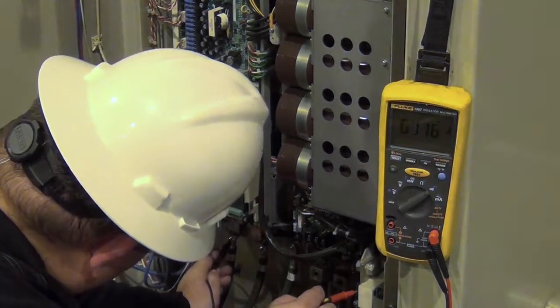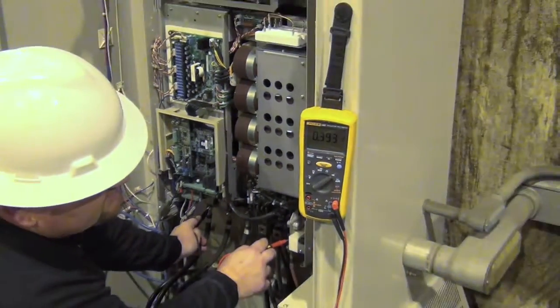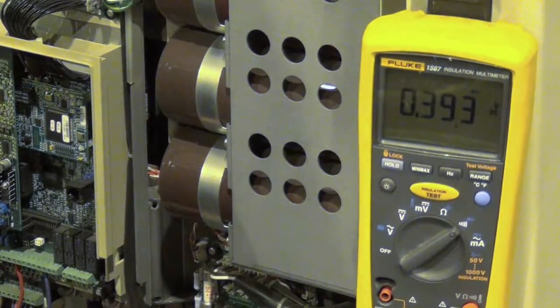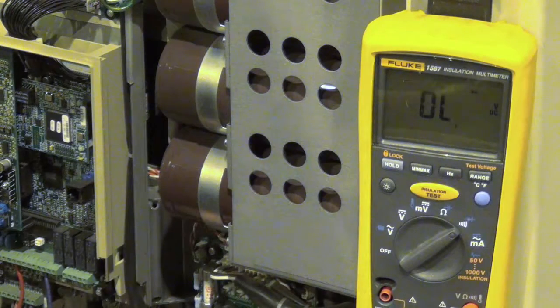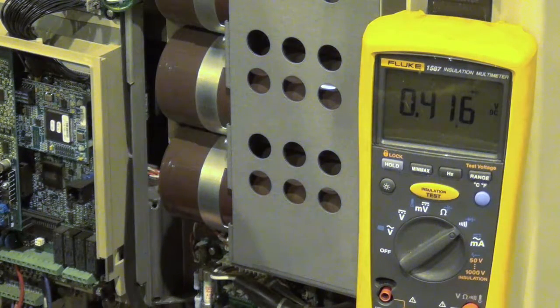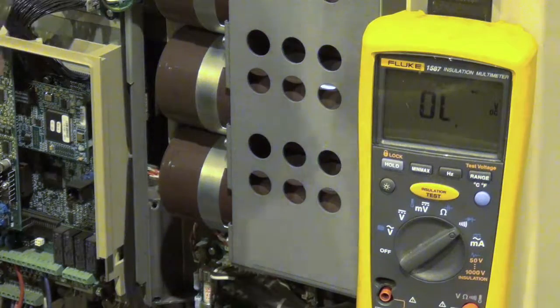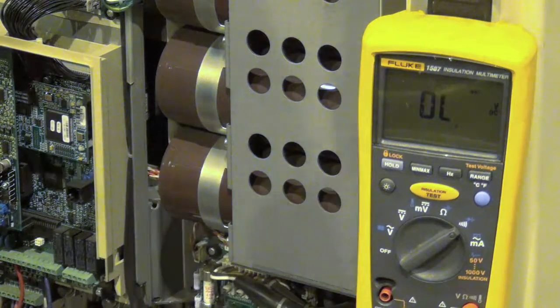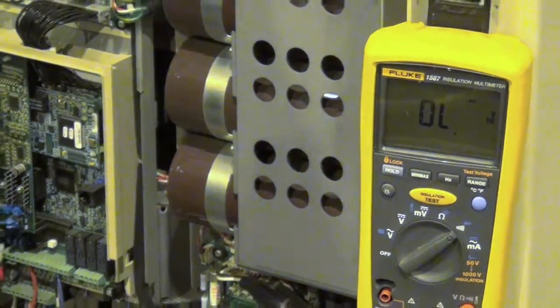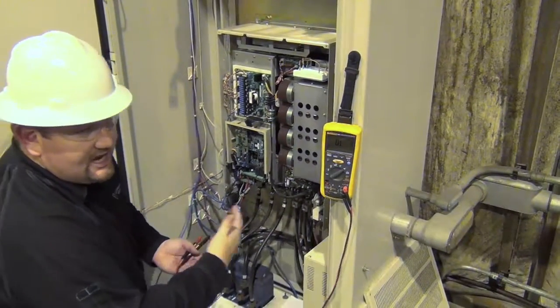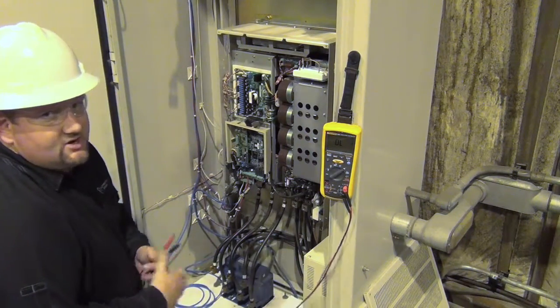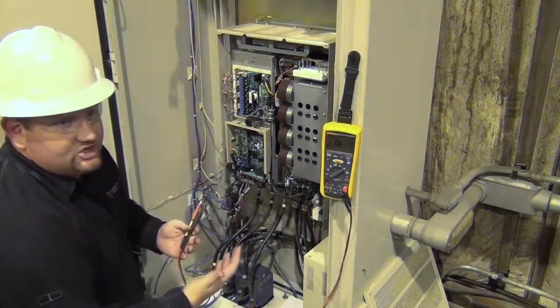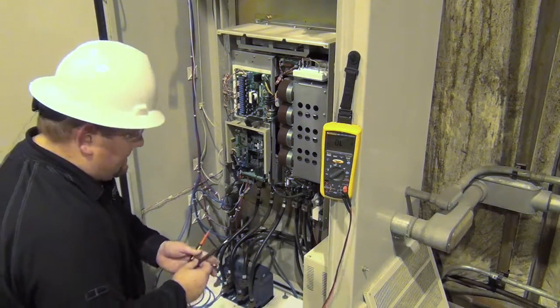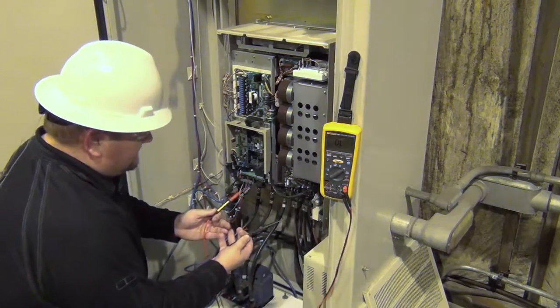And I'm going to go down here to L1, and I touch it on, and you see I get 0.393, so again, that's pretty good for a diode. With 0.4 would be theoretical ideal. Again, 0.396, and 0.416 on this one. So again, they're all pretty close, and they're around the 0.4. It varies by drive. The big portion of this is if you do the same drive year over year, you should be concerned if you see any sort of major swing and change in this value from one maintenance cycle to the next. So now what I'm going to do is just swap the leads on my probe.